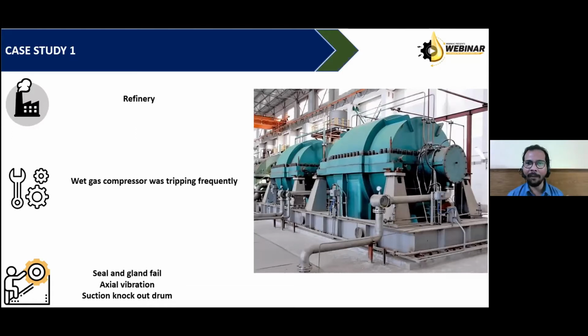Behind the fine clearances, we have bearings and the lubrication system. So whenever gas is compressed, whatever precaution we take, a small quantity of air or gas, whatever media we are using, will enter the lubrication chamber.